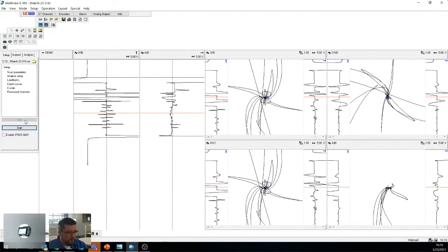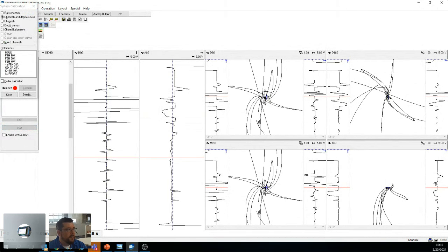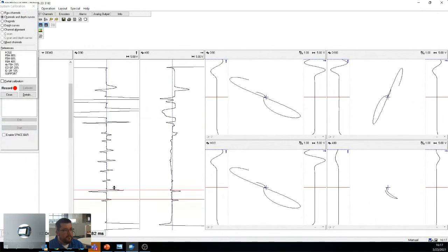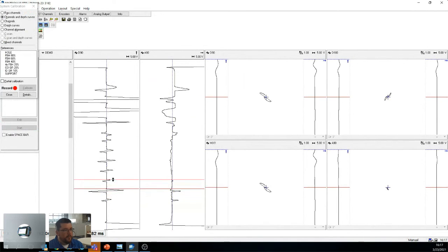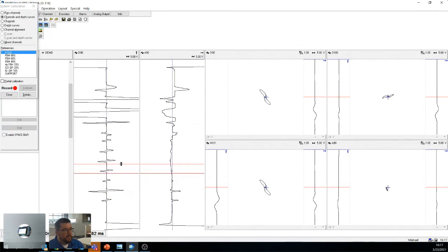So, like I said, in this case, my scan looks pretty good. I'm just going to go into my channel calibration. And what's nice with the cal tube is that, like it or not, you know what you scanned, right? I have all the information in front of me. I know that's an ID. I have 2 holes, so that's the big hole. I'm going to use a small hole to calibrate myself on. So I'm going to use this hole, record. Then I'm going to go here.